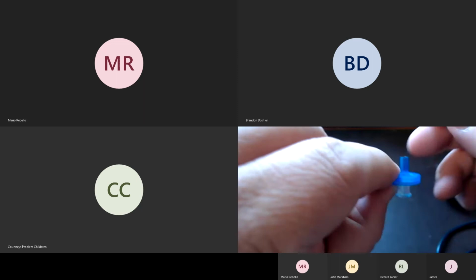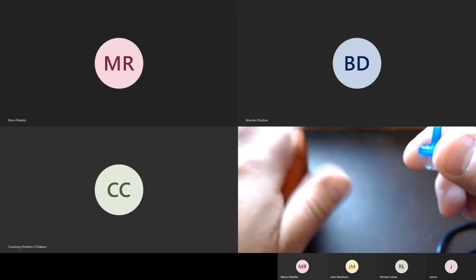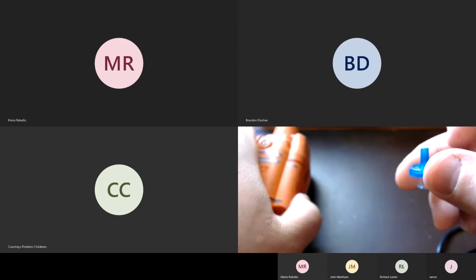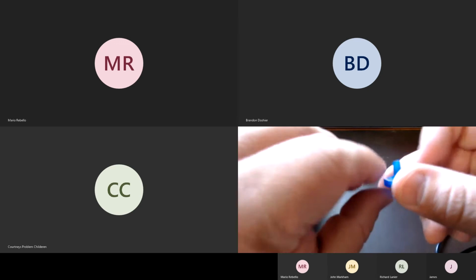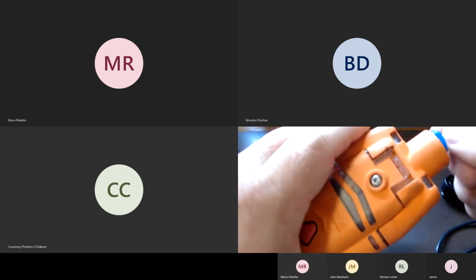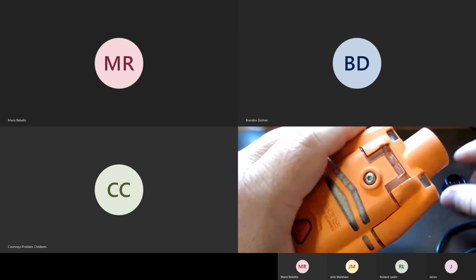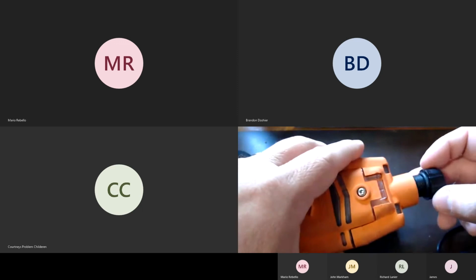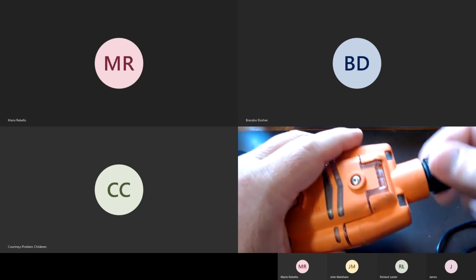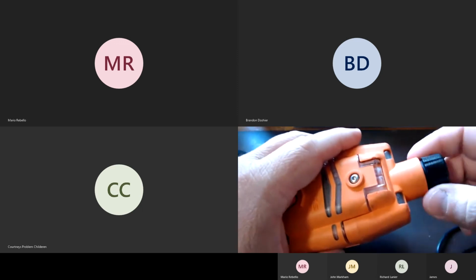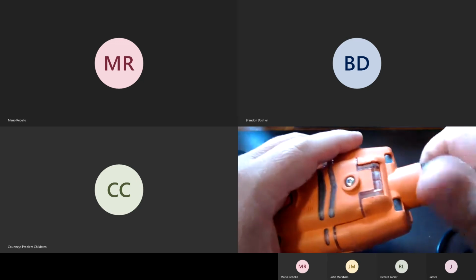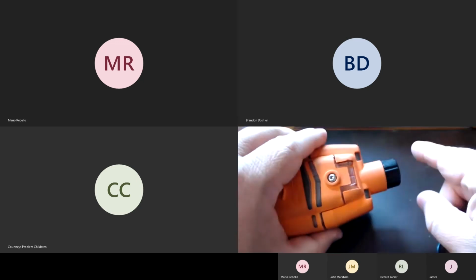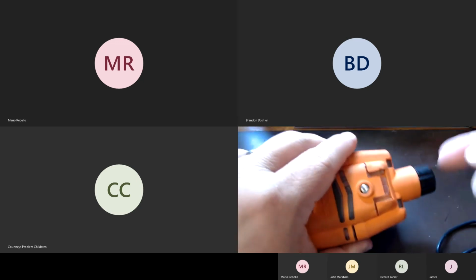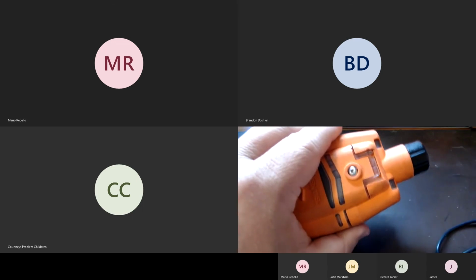Basically what I mean by that is this is there to stop whatever's getting into the instrument, but this is not your primary filter. So if you're doing a confined space sniff before you go down into a manhole or any type of confined space, make sure that on your tubing, on the end of the tubing, you have another filter. And when I say the end of the tubing, I mean the end that you're putting down into the hole, not the end that goes onto the cap.